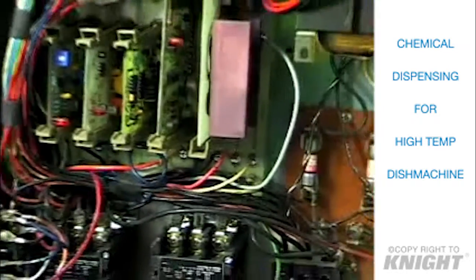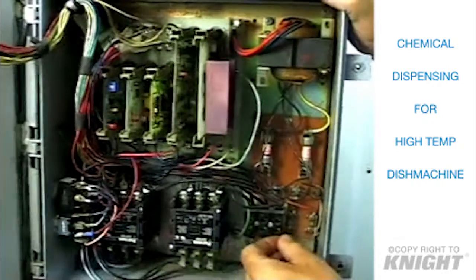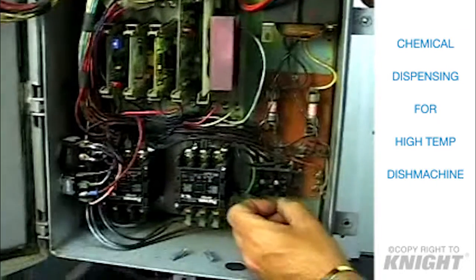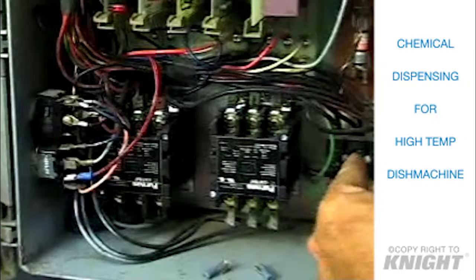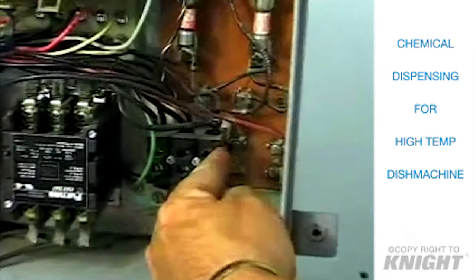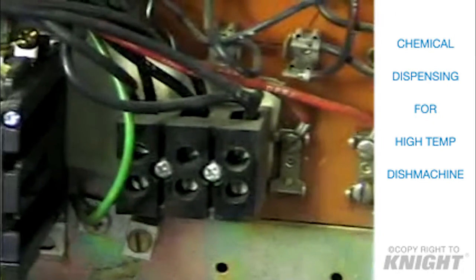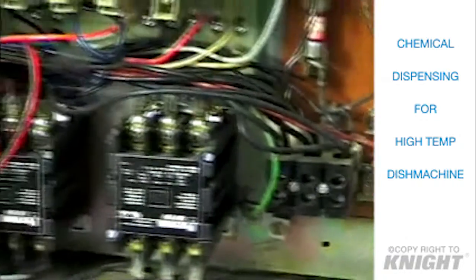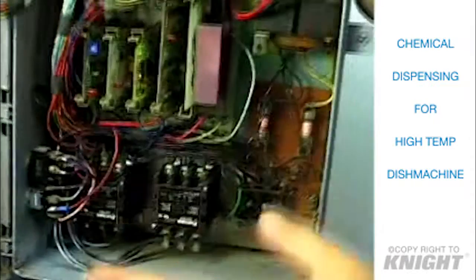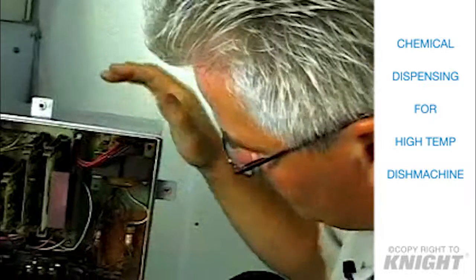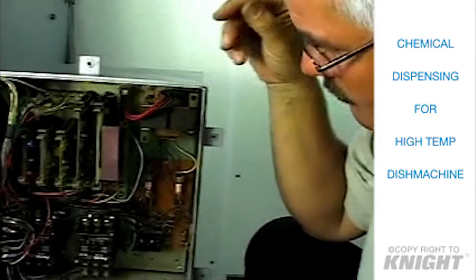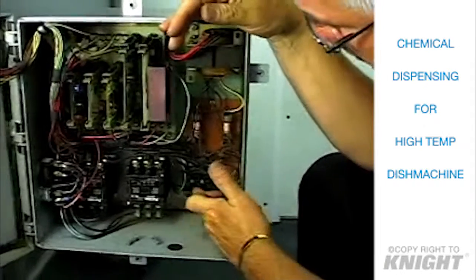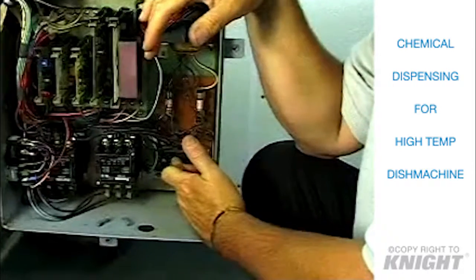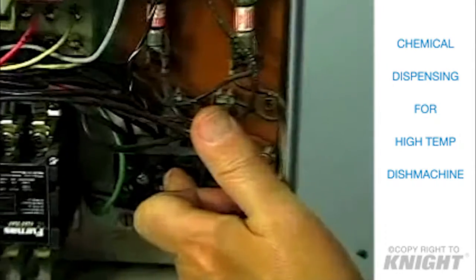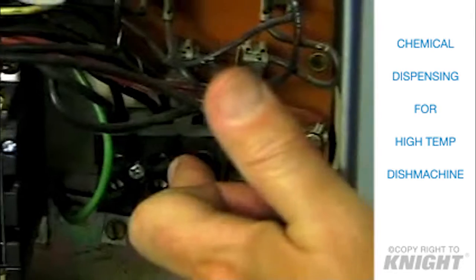And then for my constant power, I can go to either line side of these two contactors, or I can go to the incoming power right over here. This machine is also 208 three-phase. Now, if I was going to hook up a probe connection, then it's a little bit different. Then what I would do is I could still use this as my incoming power for my Digiset, because if I want to have my control lit all the time, I need constant power.